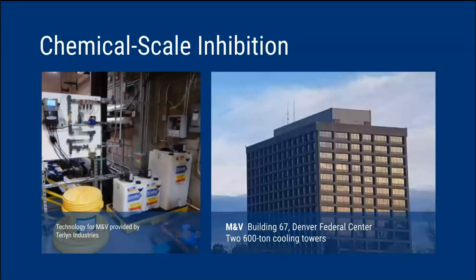So the second one that I'm going to go through today is what I would characterize as a more traditional water treatment system. This is manufactured by a company called Terlyn. So unlike the other 3 technologies that we're going to discuss today, this one does use chemicals. You can see the 3 different vats of chemicals that are used in the picture on the left-hand side, and we'll go into the differences in the types of chemicals on the next slide. This particular system was installed at Building 67 at the Denver Federal Center. This is about a 340,000 square foot office building. Again, they had two 600-ton cooling towers, and they also had the water side economizer. Okay, next slide.